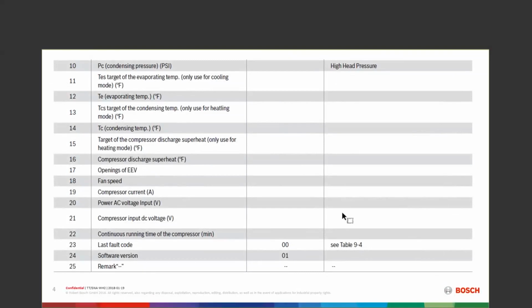On the rest of the page, I'm looking here from parameters 10 to 25. You can see that I have some new ones on here. Number 18 is my fan speed. On this particular one, it would be one of 10 numbers. If I had the 1.0 3-ton unit, it's going to be one of 2 numbers. That's a 4 or an 8, low speed, high speed. If I had a 1.0 5-ton unit, it's going to be one of 8 numbers. There's your 8-speed ECM motor. But on the 2.0, 3-ton and 5-ton, it's going to be one of 10 numbers.